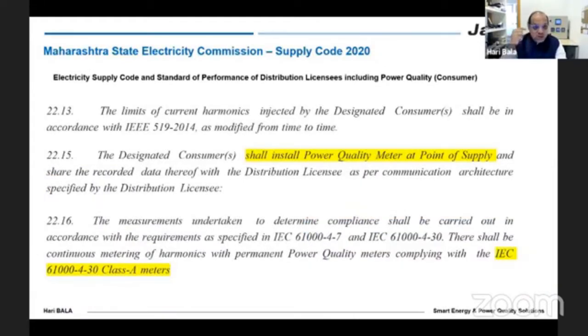Further, the supply code says that the limit of current harmonics injected by designated consumers shall be in accordance with IEEE 519. So there is a limit in IEEE 519 which has come up. I will be taking up what the limits are in the next few slides. The designated consumers shall install a power quality meter at the point of supply and share the recorded data thereof. So they have asked us to have a power quality meter at the point of supply, and then we should start monitoring it.